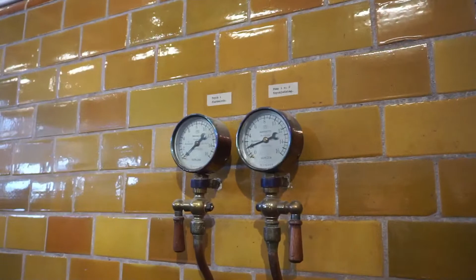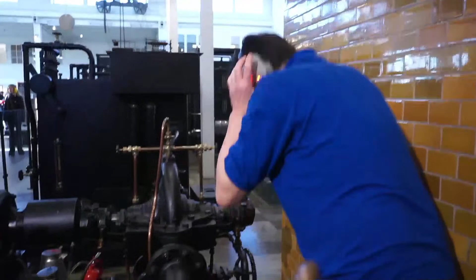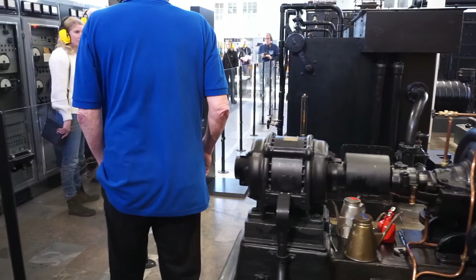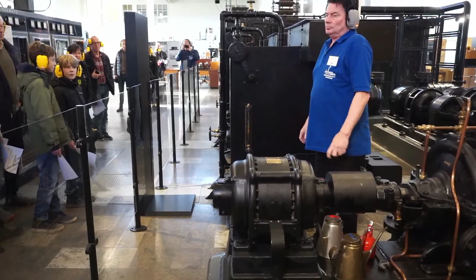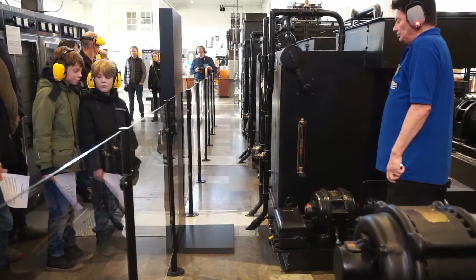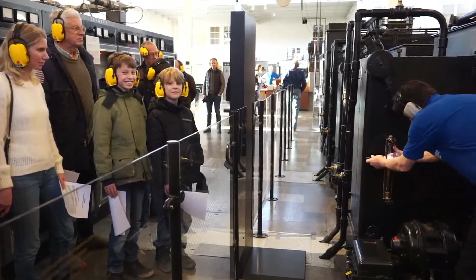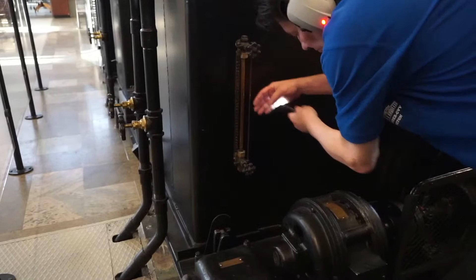The cooling system is rather complicated. We have water tanks outside the building, and water to the pump is supplied from these tanks. And the cooling system is working in a closed loop. So from here it goes through 2 liquid resistors and then up to the alternator, the magnetic amplifier, and then back again. Now Anders is controlling the liquid resistors to check that we have enough liquid. It will get hot and evaporate, so sometimes we have to add some.